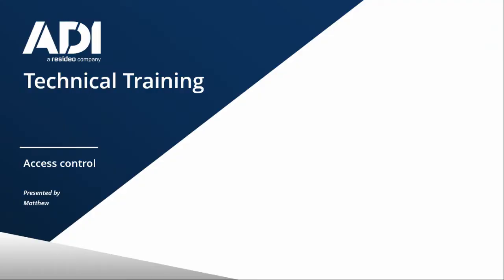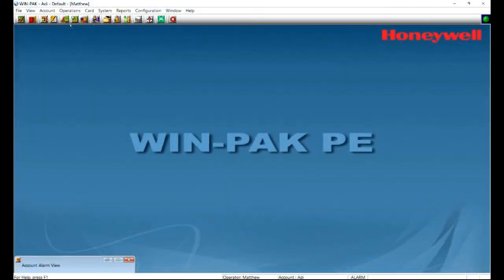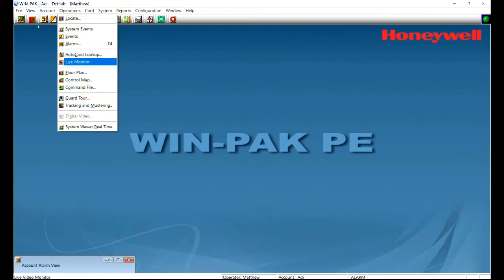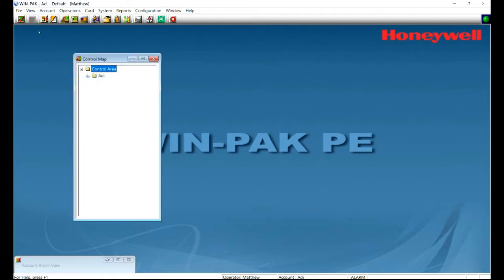In this video, we're going to update the firmware in the Netaxs123 controller. We're going to be using the WinPak 4.9 software to perform the update. With WinPak open, we just go to Operations and Control Map, and that will show us the controllers we have online here. You see I've got two. So let's go to the top one.